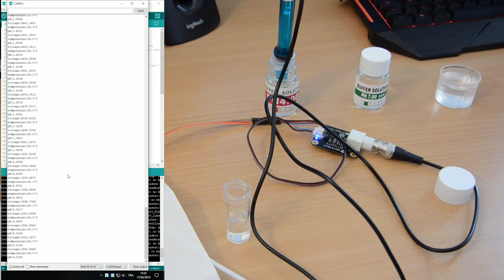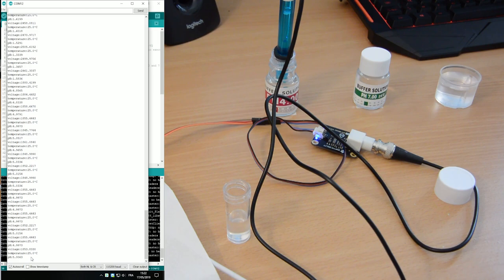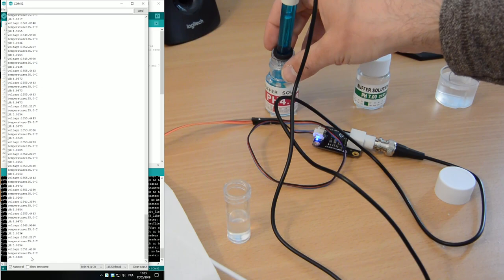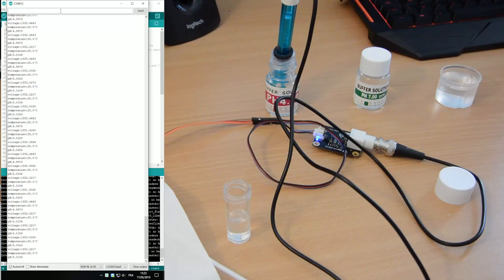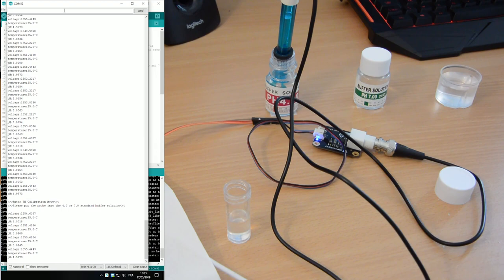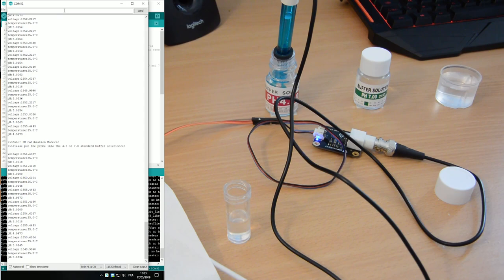Important fact also when you use a solution like that: you use it only once because after that it will be spoiled. So here is pH 4. So now we have to check the reading on the other side. So here we are in our sketch. And it doesn't read 4 for the moment. So let's wait a bit so it stabilizes. So it reads nearly 5. Now what you have to do is put a command right here. So you type enter pH. It goes into calibration.